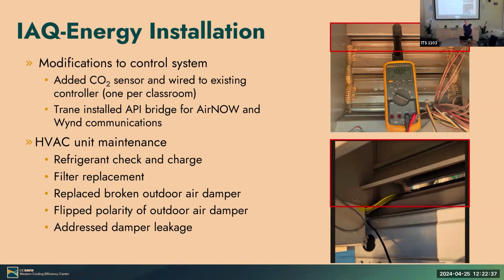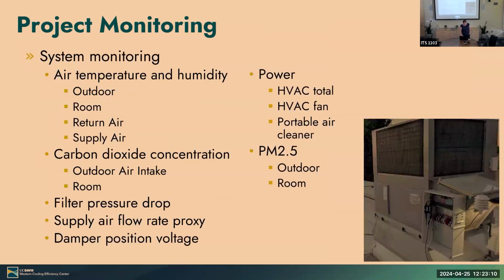Yeah. Sorry, I keep interrupting you. That's okay. Yes, that's my experience all the time. Economizer control rarely works. If the outdoor air assembly doesn't do what it's supposed to do, then controlling it serves no purpose. It wasn't really that much work to fix these things, maybe an hour. Tim was there, and he MacGyvered everything.